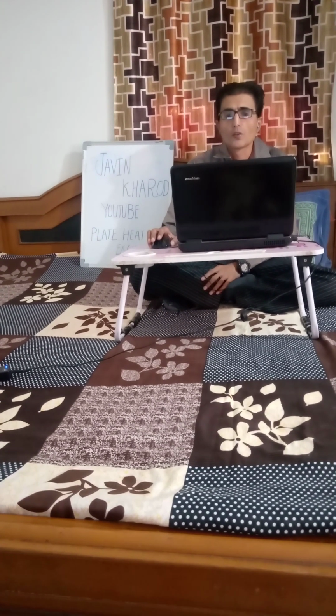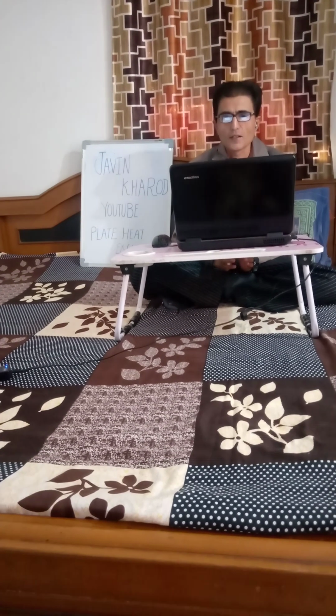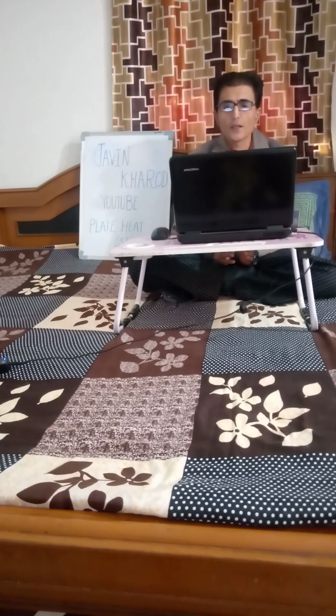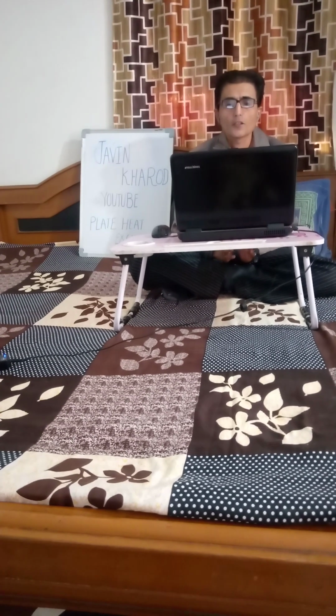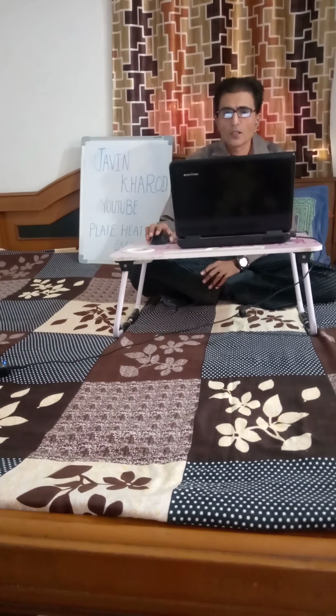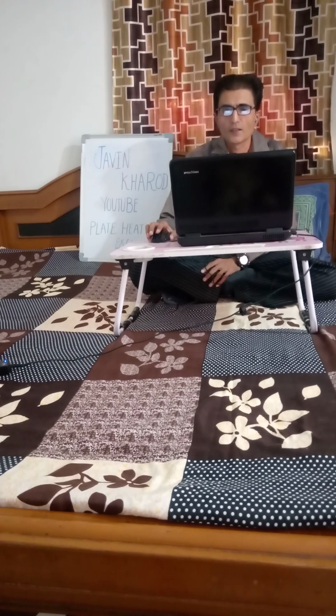For various ranges of Reynolds number, many correlations and angles for plate heat exchangers exist. The plate geometry is one of the most important factors in heat transfer and pressure drop in a plate heat exchanger. However, such a feature is not accurately prescribed in the corrugated plate heat exchanger because of the narrower path between the plates. This causes large pressure drop, and the flow becomes turbulent along the path, therefore requiring more pumping power than other types of heat exchanger.